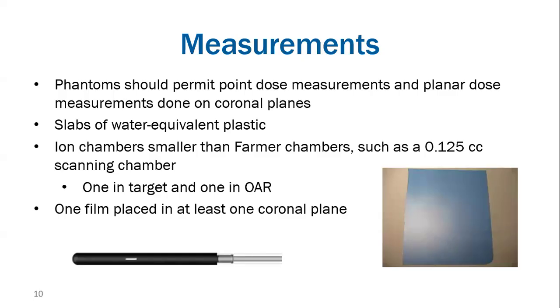That will be sufficient. They recommend that the ion chambers be smaller than Farmer chambers, such as the 0.125 cc scanning chamber. This is because when we are making measurements for IMRT, right, often we are using small fields, so we can be in the realm of small field dosimetry, which, again, if you want to go deeper into small field dosimetry, we had a talk on that about 2 years ago as well that you could find on the YouTube channel.